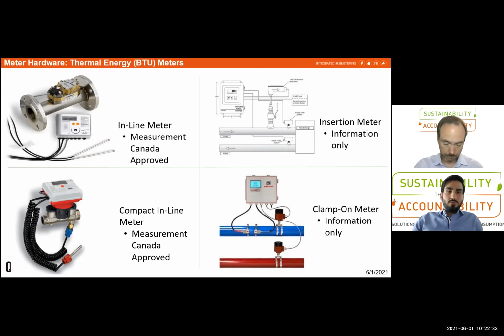On the top right, insertion type meters, which could usually be used for energy management applications, offering significant cost savings when it comes to larger pipe sizes, around 8 inches or more. This type of meter typically can be hot tapped and installed without any interruption or shutdown within the system. However, we need to keep in mind that periodic maintenance is necessary for accurate measurement of this type of meters.